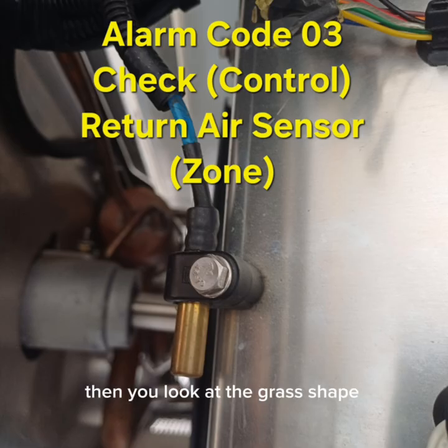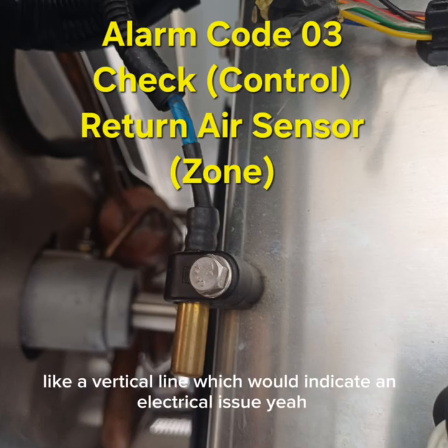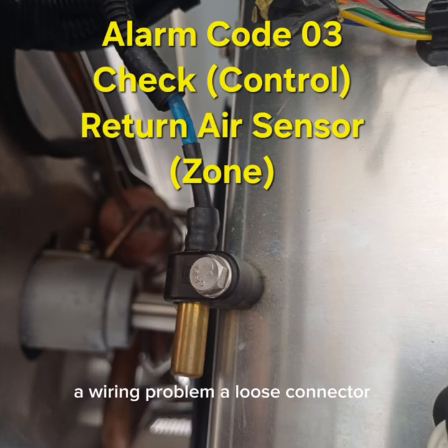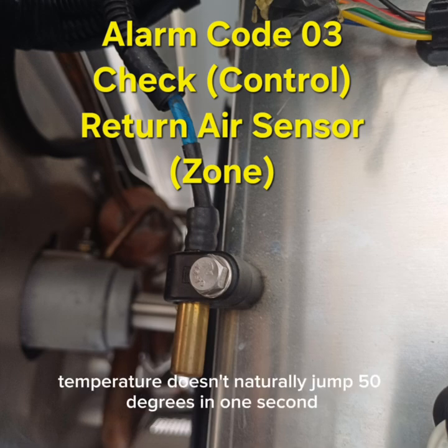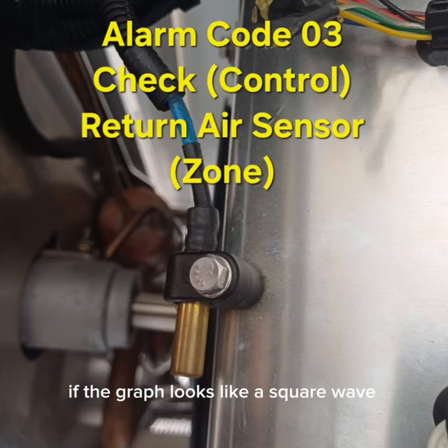Then you look at the graph shape. Did the temperature spike instantly, like a vertical line? Which would indicate an electrical issue. Yeah. A wiring problem. A loose connector. A vibration causing a momentary short. Temperature doesn't naturally jump 50 degrees in 1 second. If the graph looks like a square wave, it's electrical.